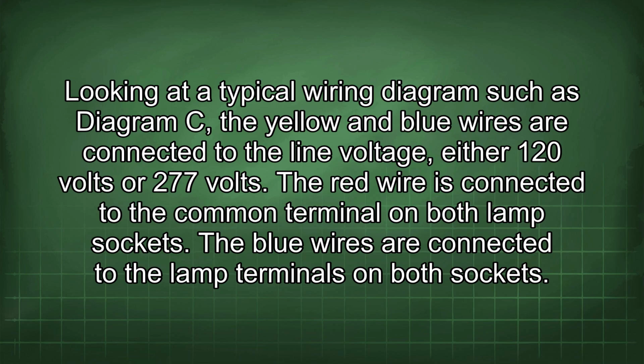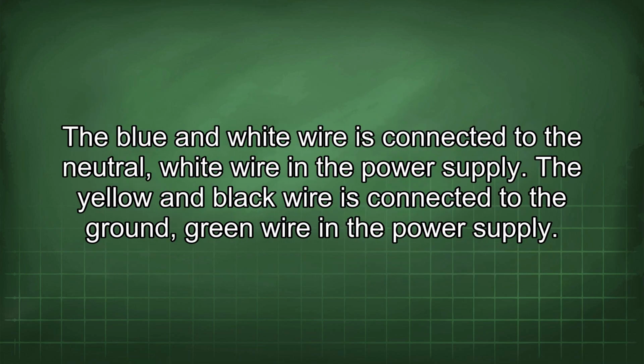Looking at a typical wiring diagram such as diagram C, the yellow and blue wires are connected to the line voltage, either 120 volts or 277 volts. The red wire is connected to the common terminal on both lamp sockets. The blue wires are connected to the lamp terminals on both sockets. The blue and white wire is connected to the neutral, white wire in the power supply. The yellow and black wire is connected to the ground, green wire in the power supply.